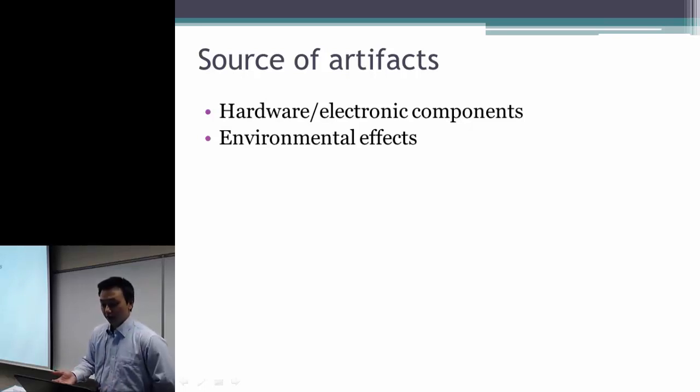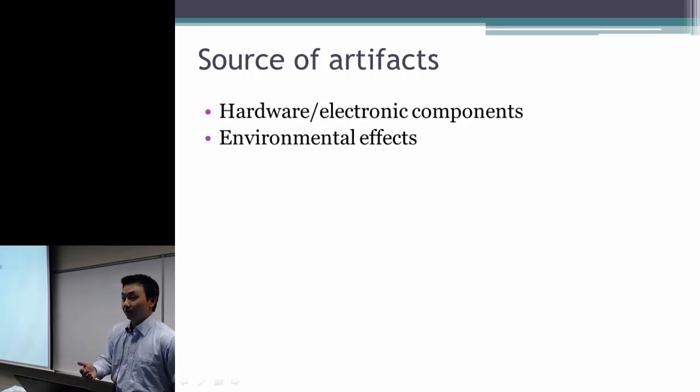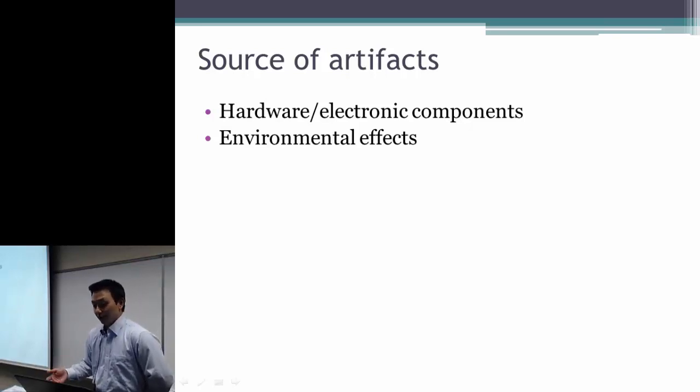And also there is environmental effect. It is very important that you choose a proper site for the MRI scanner. If you put your MRI scanner next to a major road with 18-wheel trucks going just outside the gates, like 100 feet away, the big chunk of metal can affect the field inhomogeneity of the magnetic field, or affect the electromagnetic integrity of the system. So it can give you some kind of artifact whenever a big truck is passing through.